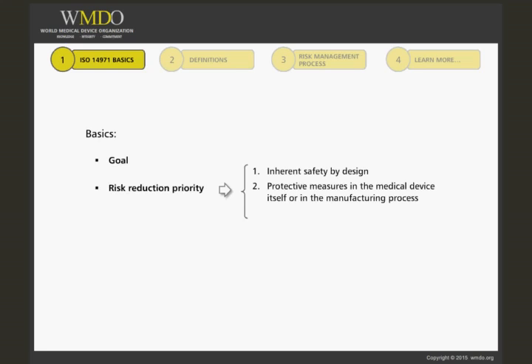Protective measures also should be taken as part of your manufacturing process — for example, in ensuring that electrical connections within your device cannot be connected the wrong way. And third, don't forget to provide information for safety in your instructions for use to help ensure the safe use of your device.